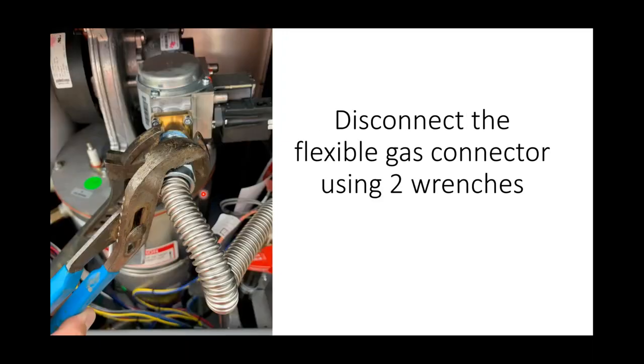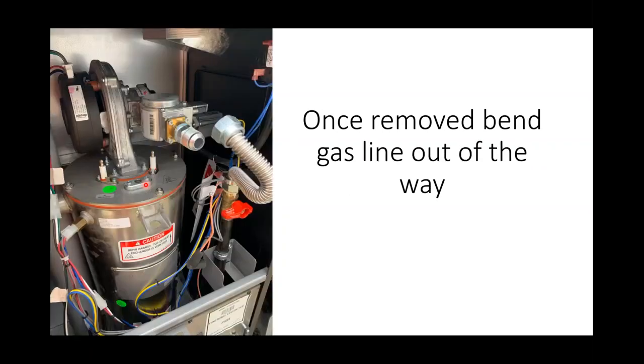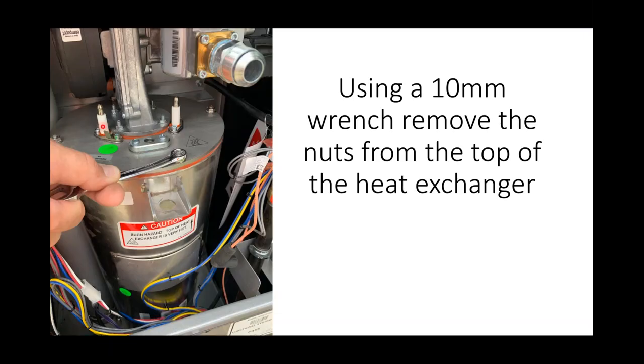Next thing, using our holdback wrenches, we're going to want to disconnect the flexible gas connector. Use your holdback, take that off, pull that flexible gas connector out of the way. Bend that out of the way, push it all out of the way. You can see now you have better access to get to these 10mm bolts, so start removing them. That'll be your next piece. The wrench is a little bit easier to use as opposed to the socket. There's going to be one bolt back in here that is going to be the first bolt you have to put back on, and the last bolt you have to take off. Be careful not to drop it down in the bottom of the heat exchanger. It likes to hide back there in that corner when you do drop it.